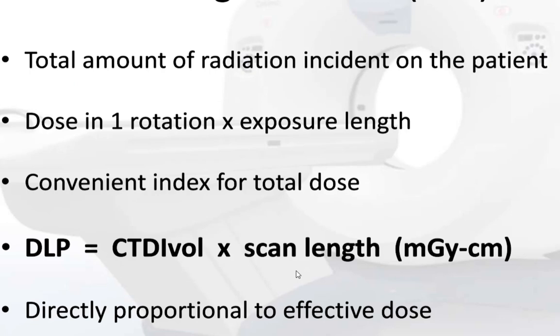Another important measurement of CT dose is DLP, the Dose Length Product. It is the total amount of radiation incident on the patient — dose in one rotation times exposure length. It is a convenient index for total dose. DLP equals CTDI volume times scan length, in milligray-centimeters, and it is directly proportional to effective dose.